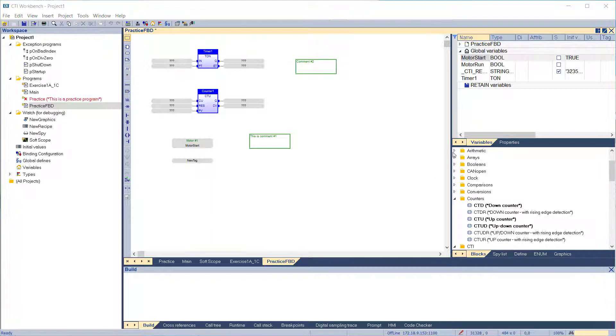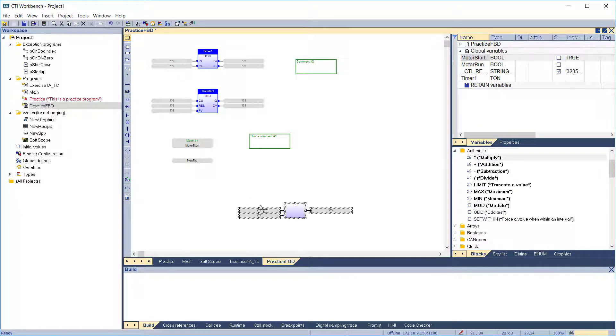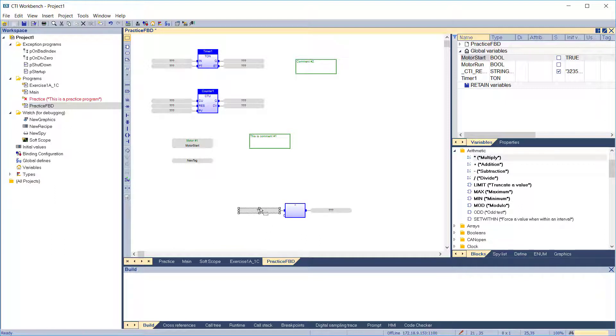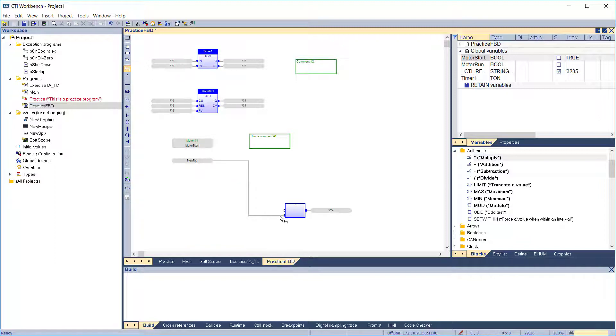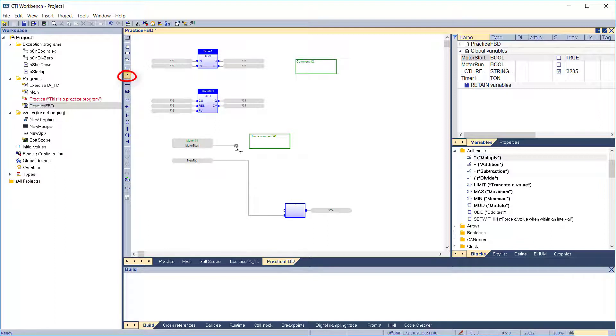There are two ways of drawing interconnection lines in the editor. We've placed a multiply function on the diagram and we'll connect the two variable tags we just created. You can use the add arc icon, which allows Workbench to automatically route the line between the endpoints. Notice that you must draw the line in the direction of signal flow. You can also use the corner icon to manually route the line.